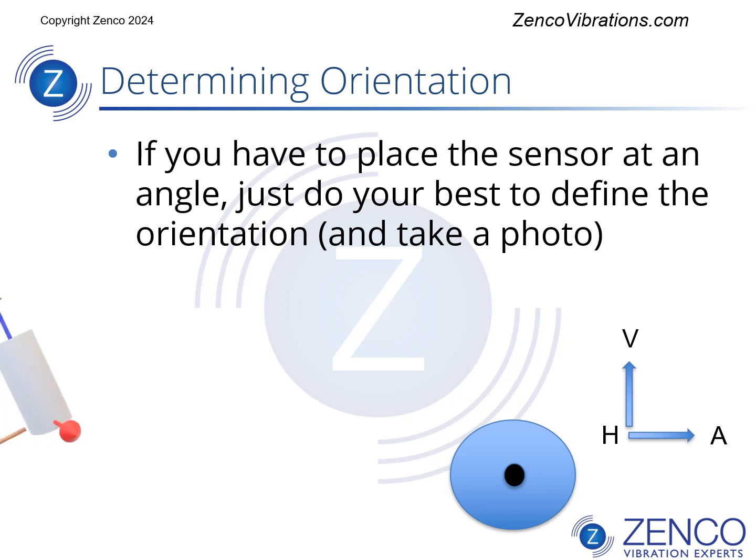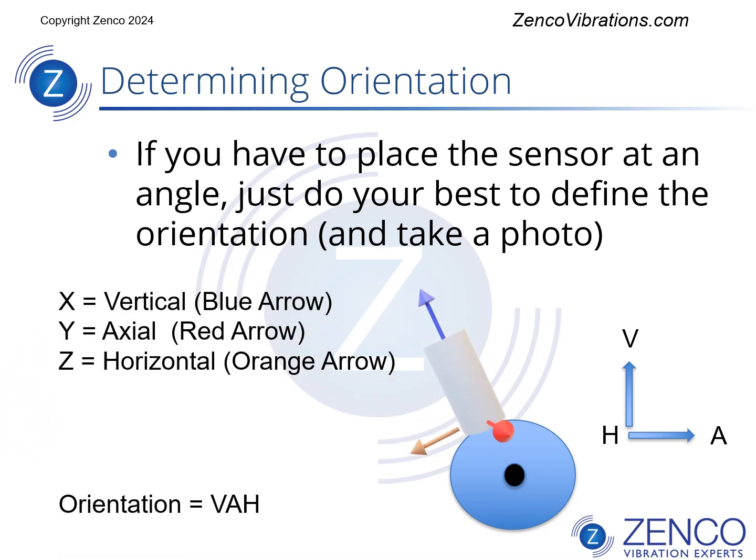Now if you have to place a sensor at an angle, just do your best to define the orientation, and perhaps take a photo or draw a picture showing how the sensor is oriented. In this case, even though we're not pointing directly vertically with the X blue arrow, we could still call X vertical, Y axial, and Z horizontal. If it was tilted a little bit more to the side, we could call X horizontal and Z vertical. The more important thing is to make sure that we get the axial one correct.